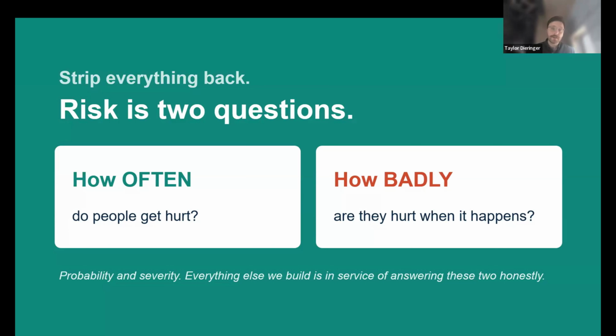So with sequence of events particularly, and we'll get into that, if we anchor everything by the individual cause, oftentimes we're splitting up probabilities in a way that could not be defendable in an audit. Another thing that the FDA shared with me is one of the worst things that you can do is, when you identify severity 5 harms and define acceptability for them, to have a probabilistic outcome as to what is acceptable, i.e. how many deaths is acceptable. Of course, the very first answer to that question is no amount of harm is acceptable for our device to cause. It is on our risk policy to define what is justifiable for what's in the field.